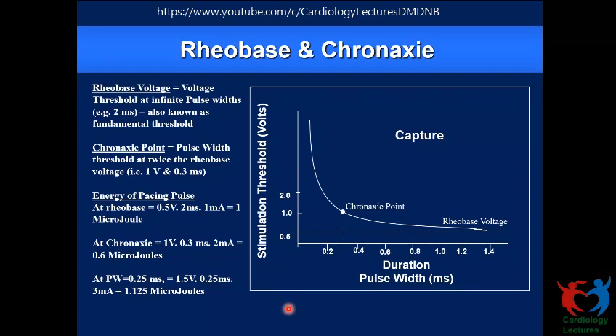That's the scientific point behind this. Because the chronaxie pulse width, as I said, is between 0.25 and 0.5 milliseconds in most pacing systems, at a nominal pulse width of 0.4 millisecond, we measure the amplitude threshold and program an output twice of that, which is reasonably good for most patients. You may have to look at this pulse width more carefully when the patient comes back with a slightly higher threshold, where you may want to check the amplitude threshold at a slightly increased pulse width, and you can increase the amplitude at that pulse width a little more so that you maintain a two-fold safety margin, but reasonably conserve the energy outgo from the battery. So that's the importance of keeping the strength duration relationship in mind while we program the output for a pacing system.